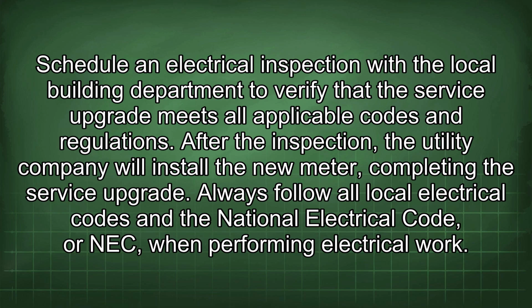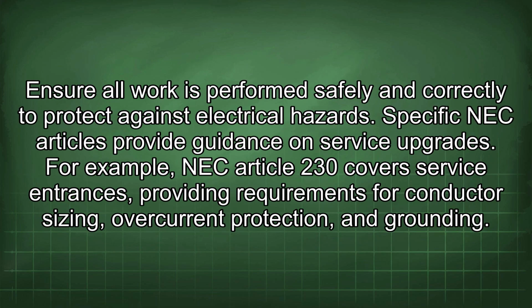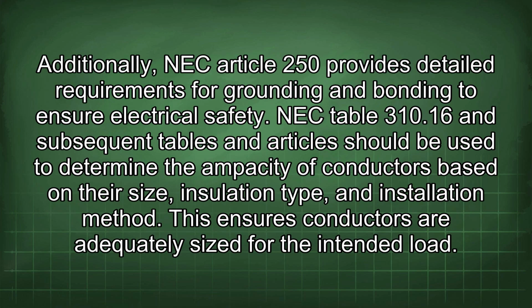Always follow all local electrical codes and the National Electrical Code, or NEC, when performing electrical work. Ensure all work is performed safely and correctly to protect against electrical hazards. Specific NEC articles provide guidance on service upgrades. For example, NEC Article 230 covers service entrances, providing requirements for conductor sizing, overcurrent protection, and grounding. Additionally, NEC Article 250 provides detailed requirements for grounding and bonding to ensure electrical safety.